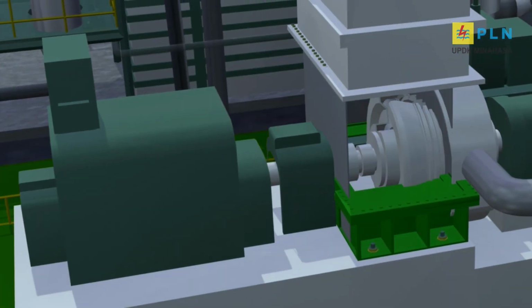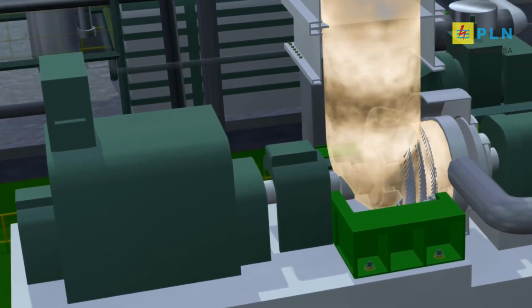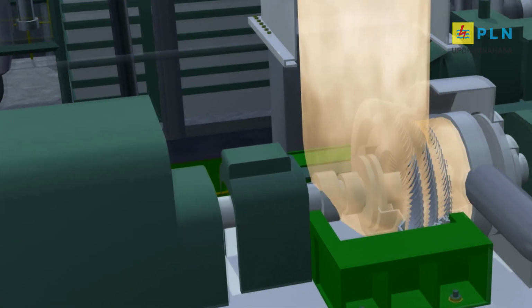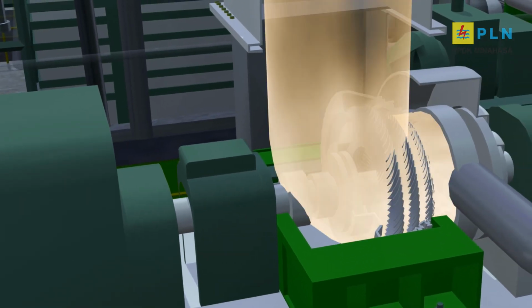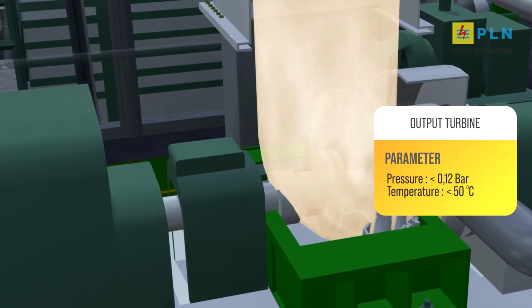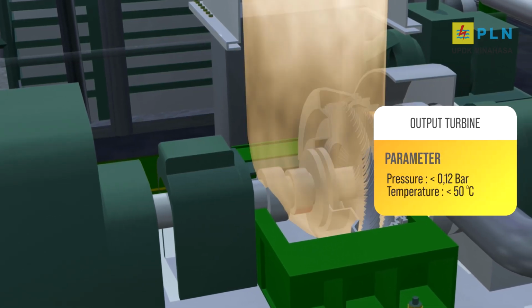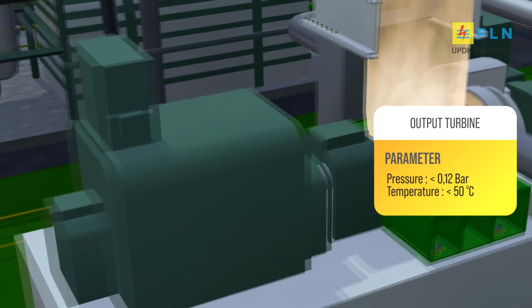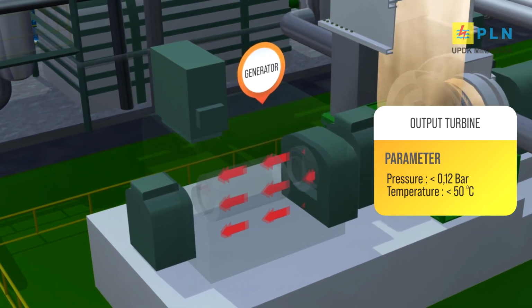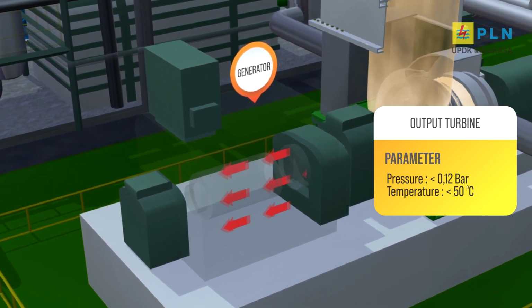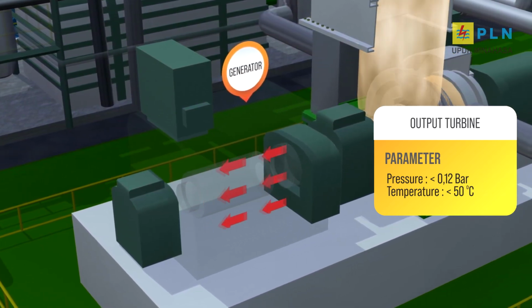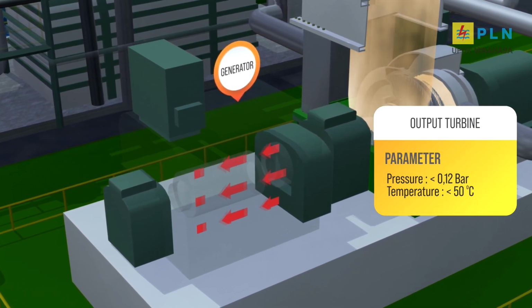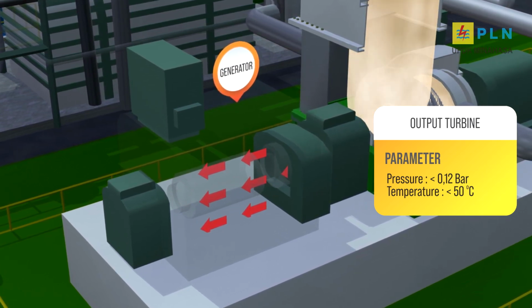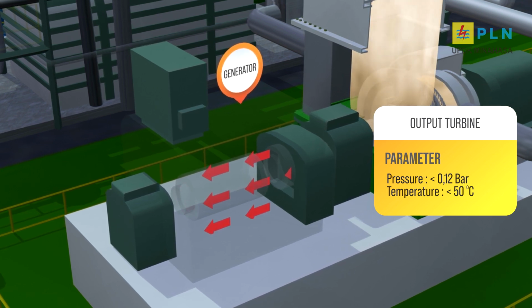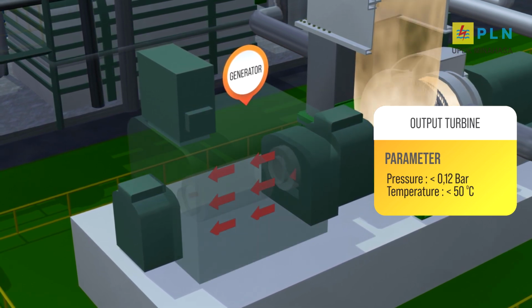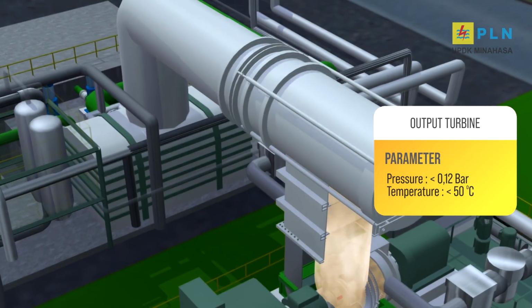The steam that enters the turbine with a pressure of 7 to 8 bar and a temperature of 170 degrees Celsius will rotate the turbine blades that are connected to the generator, converting potential energy into kinetic energy. Then the kinetic energy that has been generated is converted into electrical energy by the generator through the principle of electric motion, with an output voltage of 11 kV before raising the voltage to 150 kV in the step-up transformer, which is then supplied to the switchgear system.